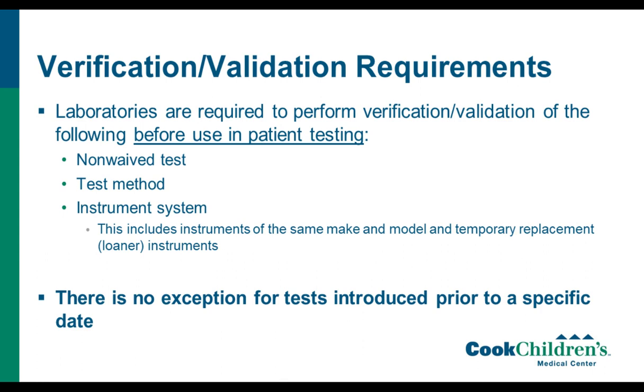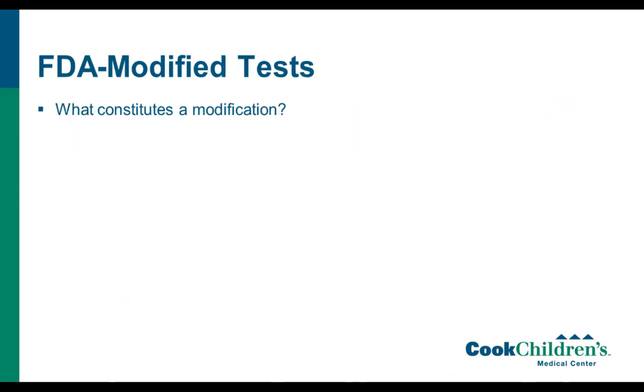And CAP specifically states that not only does this include instruments of the same make and model, but also loaner instruments. So if something happens to your instrument and the manufacturer gives you a loaner instrument, you actually have to validate that as well. And there's no exception for tests introduced prior to a specific date. So if you have a test that was introduced back in maybe the early 2000s, you still have to have verification or validation records for that as well.